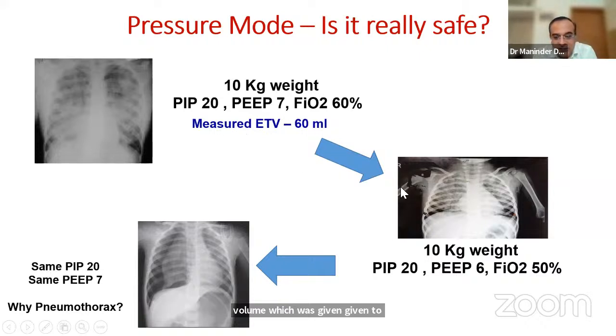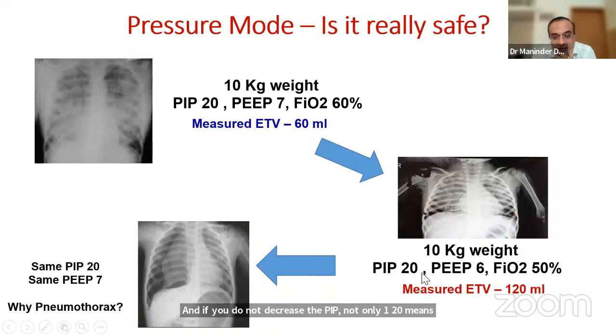As the patient improved, if you continue the same PIP, the tidal volume now becomes 120, which is very high for a 10 kg child. If you don't decrease the PIP, you'll land in trouble. So it's important to understand that pressure mode is not a safe mode — pressure mode or volume mode, both are equally dangerous.